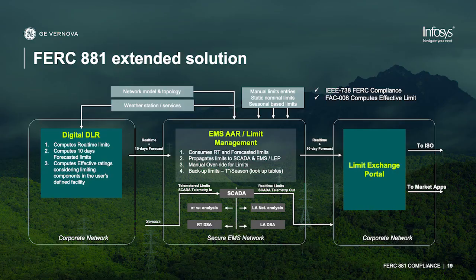So, an extended solution. Like we mentioned, the minimum requirement would be the EMS AAR limit management, which is our RTDyne application. It takes all of your limits, be they ambient adjusted ratings or dynamic line ratings from field sensors or our digital dynamic line rating application, and ensures that the correct rating with the best data source is being used at all times. The digital dynamic line rating acts as an enhancement to that, so you're getting even more capacity on your transmission system, reducing the congestion on the grid, as well as unlocking your full footprint with a single software solution installation.